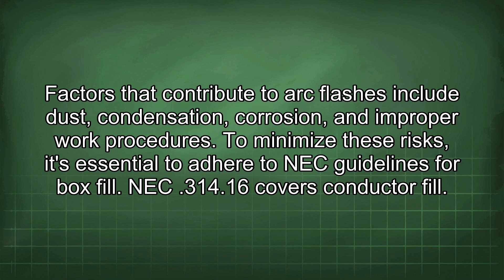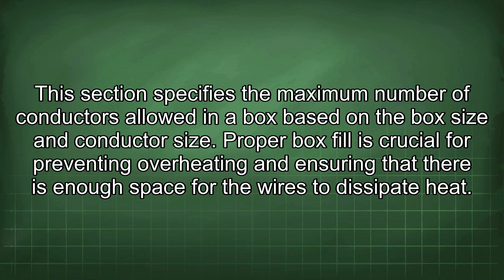To minimize these risks, it's essential to adhere to NEC guidelines for box fill. NEC 314.16 covers conductor fill. This section specifies the maximum number of conductors allowed in a box based on the box size and conductor size. Proper box fill is crucial for preventing overheating and ensuring that there is enough space for the wires to dissipate heat.